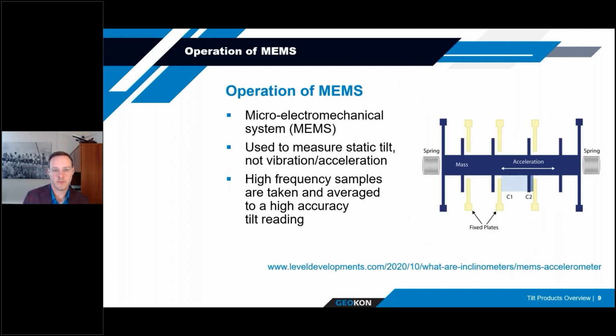So the operation of the MEMS accelerometer is actually quite similar to the servo-based accelerometer in the sense that there's a mass supported between 2 springs, and really we're measuring the position against a fixed reference. Again, these are used to measure static tilt, not vibration or acceleration. There are very specific MEMS chips that would be used for those types of measurements.